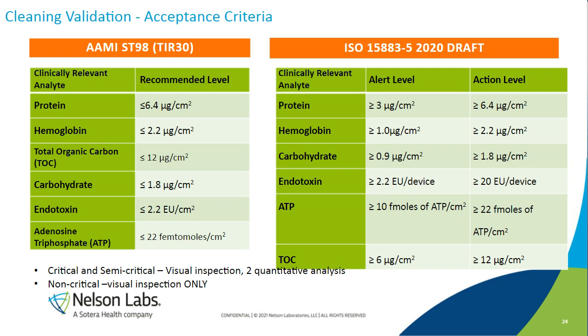ATP usually is not used for cleaning validations. It's mostly used for R&D. This is what healthcare facilities would use to assess their processing steps. It's a quick study where they give you a value in RLU, which is relative light units, and per test kit they will tell you what to multiply with to get the femtomoles per centimeter squared. But that is a value that you should achieve. I would see this more for R&D work or healthcare, or just to see where you're at. This is the benchmark you should be at.